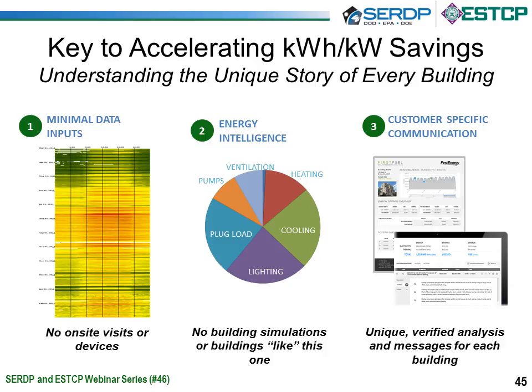So that remote audit tool that I just referred to in the life cycle of energy efficiency was the focus of our ESTCP demonstration. Our audit solution allows us to take minimal data inputs from our customer. We just need the building's address, 12 months worth of interval electricity data, and a brief building information survey completed by the site manager. We then combine that information with detailed weather data and GIS data to perform an analysis of how the building responds to changes in occupancy and weather, and then we're able to use that to come up with a breakdown of how the building is using energy down to its 7 major energy end uses. That allows us to see where there are opportunities for savings.